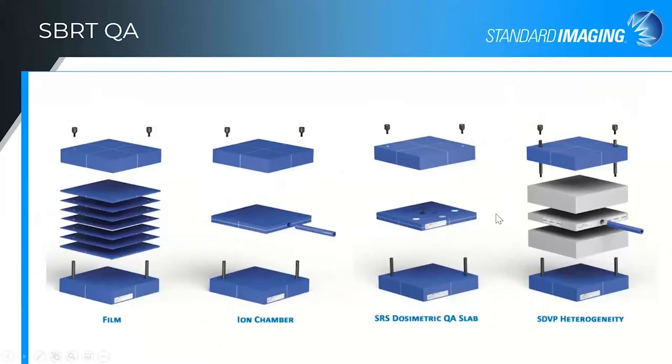And here I wanted to just show you the versatility of our stereotactic dose verification Phantom, which is a 20 by 20 Phantom. So it's easier to manage, easy to set up. We're locking things into place so things don't slide around. There are embedded fiducials in the Phantom configured in a nonlinear, non-coplanar fashion to create an isocentric volume. Our chamber plug also has gold fiducials, which are, again, closer in because they're on that plug, so that's better for the smaller tumors that you're tracking.